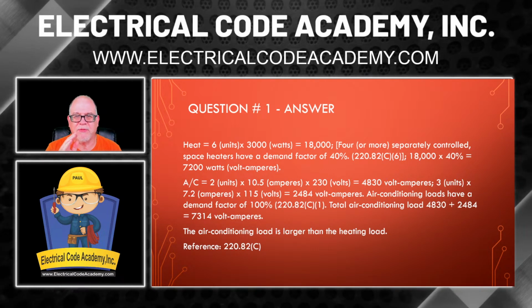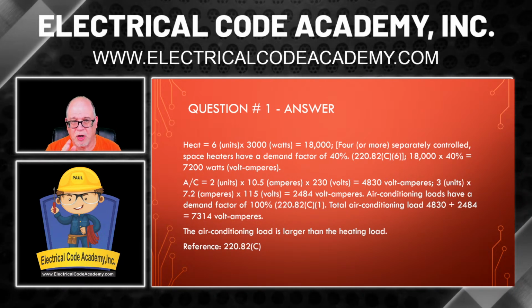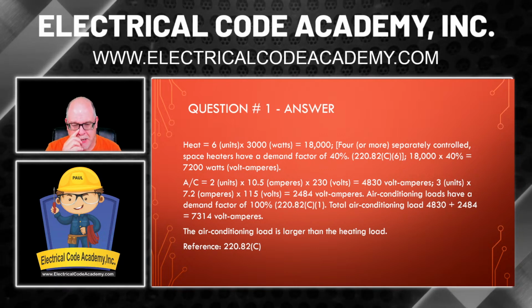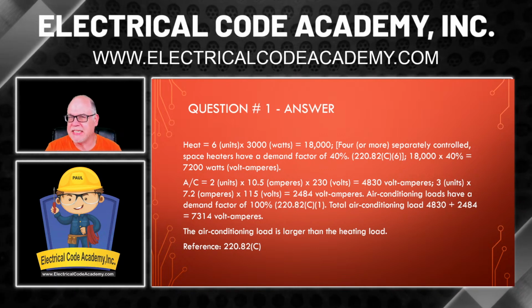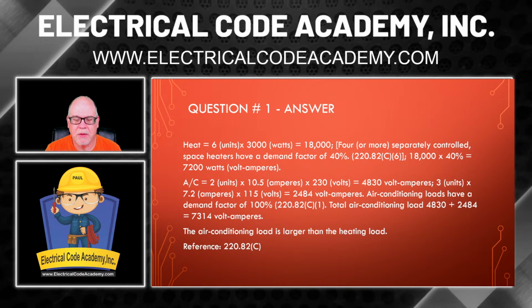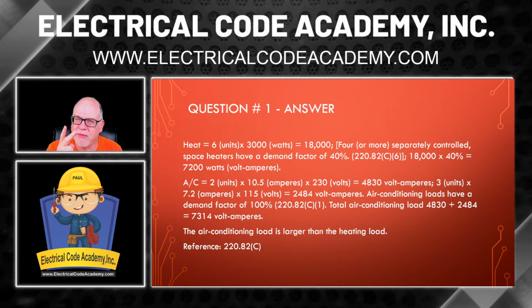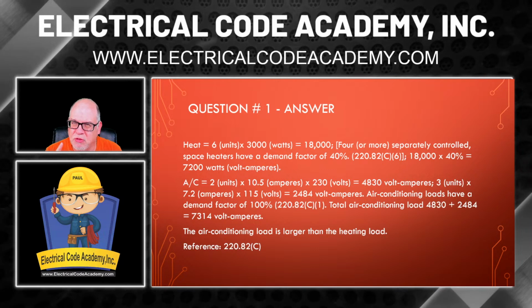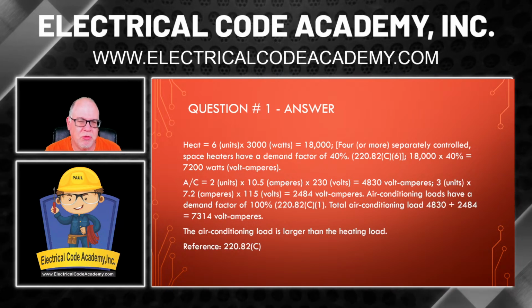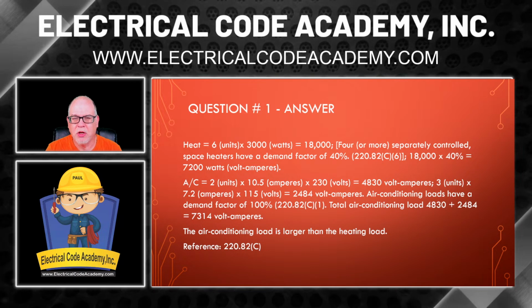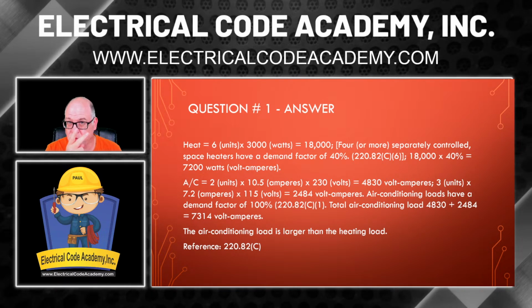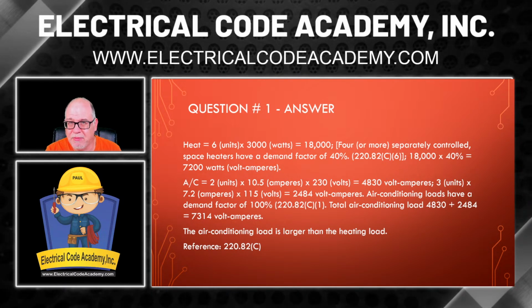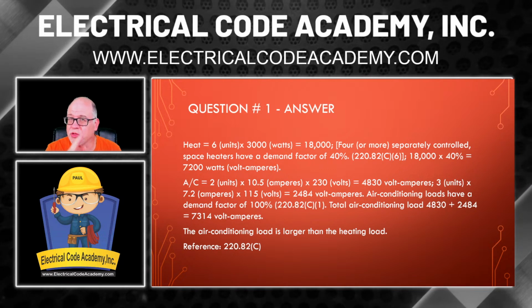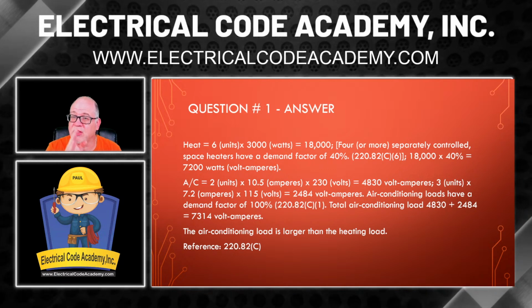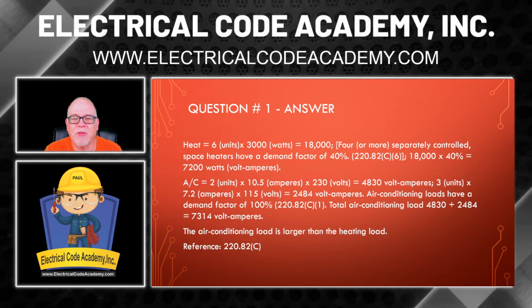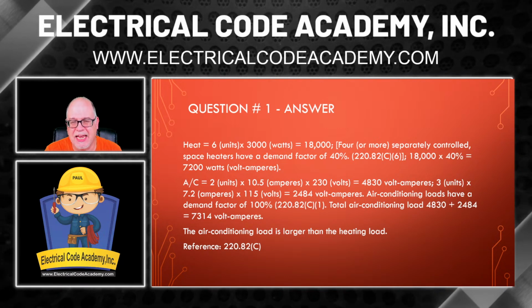Now let's look at that AC, because we know that we've done the heat already, and 7,200 is what we're working with for the heat. Is that going to be greater than the AC? Well, that's what you've got to work out. Remember, we had 2 of them at 10.5 amps each, and 3 of them at 7.2 amps. So easy math: 2, because there are 2 of them, times 10.5 times 230 volts. Remember, use the voltage that's given in the question. That's going to give us 4,830 VA.